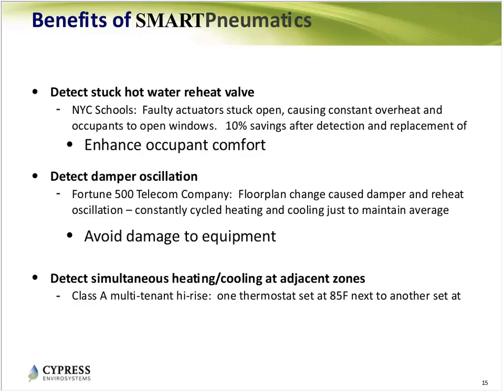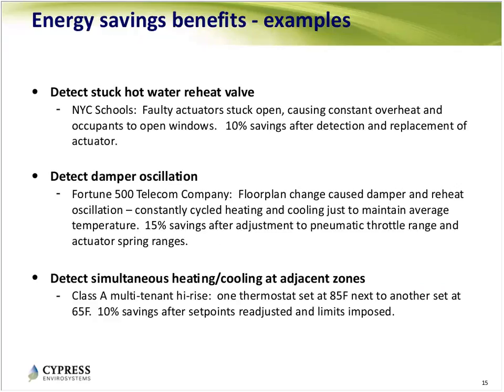I think I'm almost running out of time, so I'll skip over some of these. Just as an example of the things you might detect: one case we had in New York City schools, they have 1,000 pneumatic schools, and many of the hot water valves are stuck. After many years—30, 40 years—the hot water valve gets stuck open, on maximum heating, and people open windows to cool down. They never knew about this, and it was overheating for years and years, wasting energy with no detection of the stuck valve.